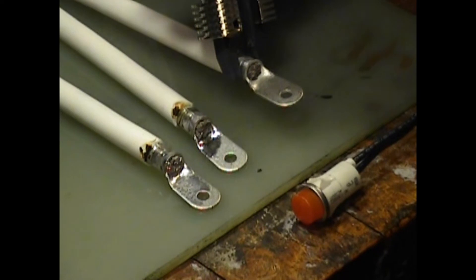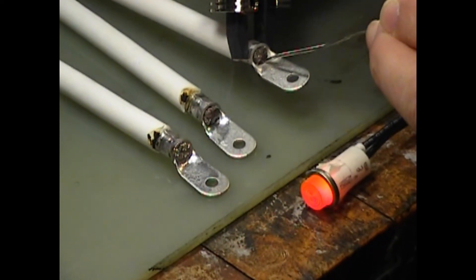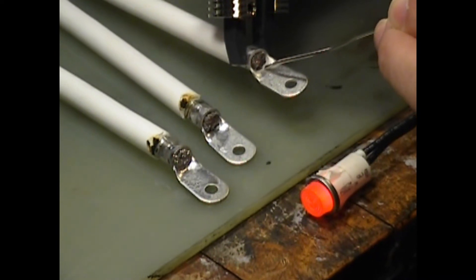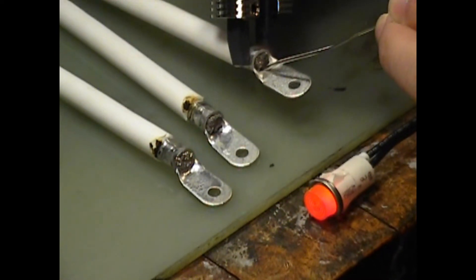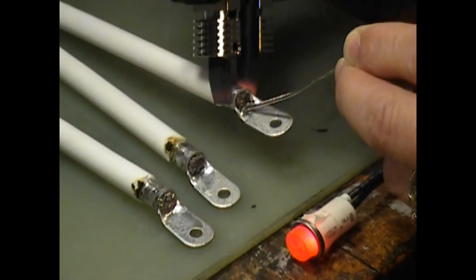The electrodes in this handpiece can be modified to meet the needs of a specific application. Using a fine tooth file or emery cloth rolled to the correct diameter, form a radius in the electrodes that matches the contact surface of the terminals or components being soldered.